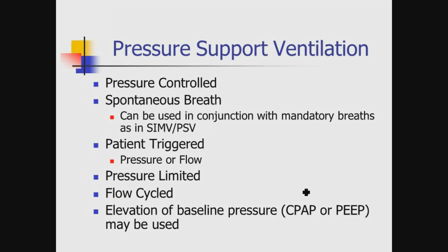Okay. So again, we're talking about a pressure-controlled breath, a pressure-oriented breath. Volume and flow become variable. It is a spontaneous breath. We'll talk about its use interspersed with those mandatory breaths later. The patient's the one that's going to trigger the breath to start it. It rises to a fixed pressure and stays there. So if I were to draw it, here's my pressure tracing. What's fixed? The amount of pressure that's being delivered.